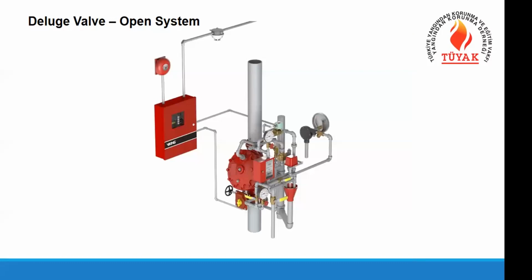And we have another system called the deluge valves. The deluge valve systems are used mainly in spray systems where we have open sprinklers or open nozzles. That means they don't have any temperature activation devices. All are open, and when you send the water from the main system or main valve, all the nozzles or openings release water at the same time. So not only the activated sprinkler, because we don't have a heat-activated sprinkler here; all of them are open, or any kind of different open nozzle device. So the water comes out from all the openings on the pipes.